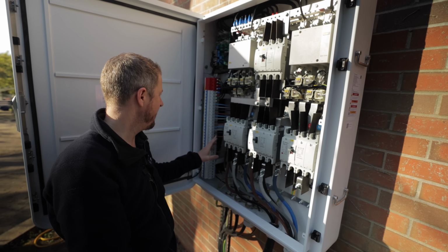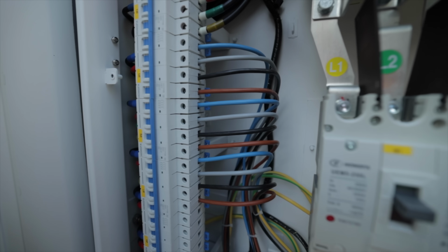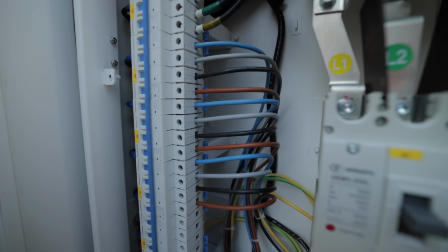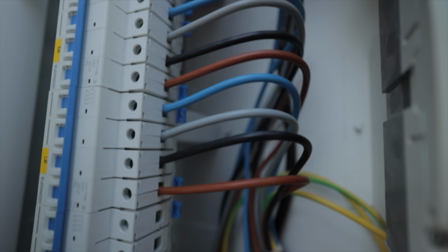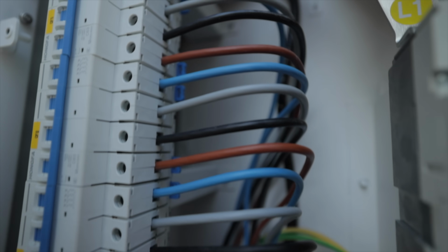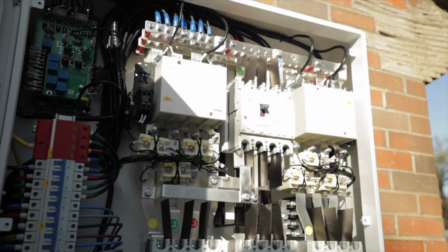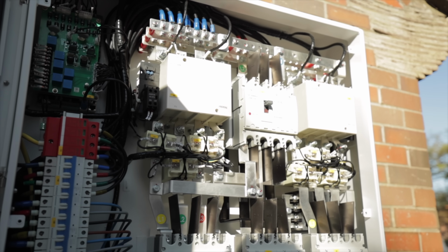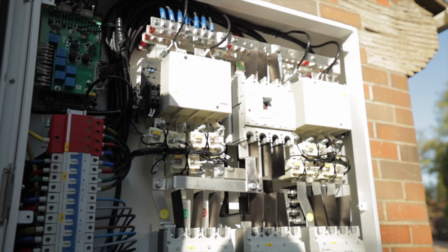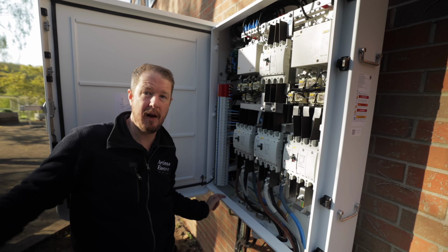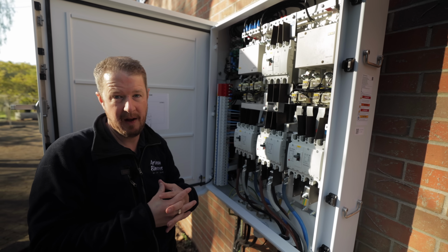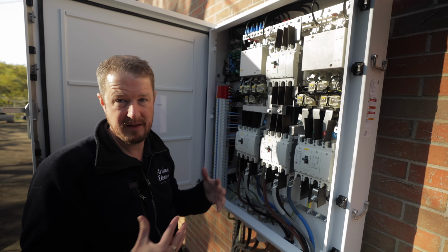In here we've installed the 3 circuits for the 3 Sigenergy stacks, each with a 10mm 5-core steel wire armoured cable going out to it. There's also a data connection that connects between this and the first Sigenergy stack, and then the Sigenergy stacks loop into each other so they can all communicate, with a hardwired Ethernet connection between them.